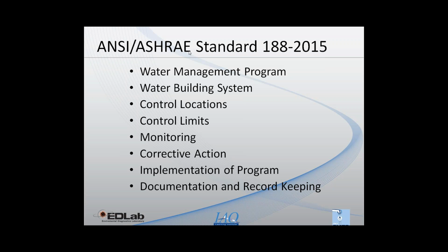But if it is a building where people are suspecting Legionella, then to minimize the risk of Legionella, a program needs to be in place, with the principle of determining whether these problems are really associated with the building water system or not. That is the first thing we need to do. Then the second point is very important, that is the building water system. The building water system needs to be evaluated for a systematic analysis of hazardous conditions in the building water system.